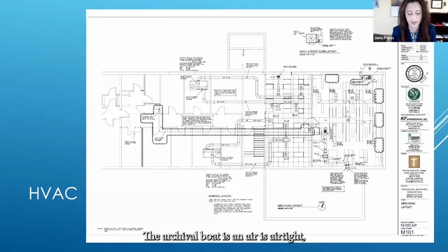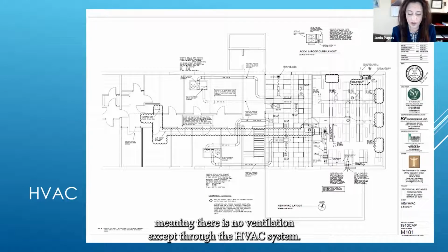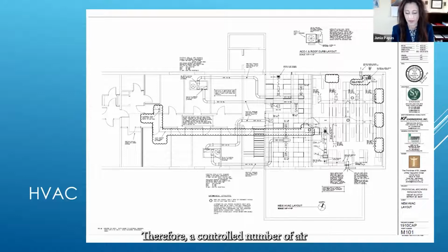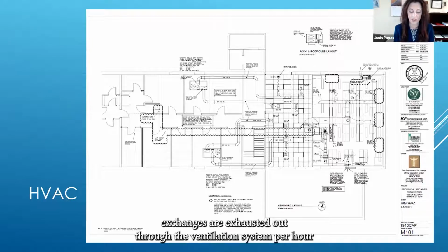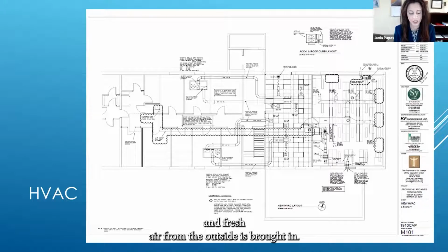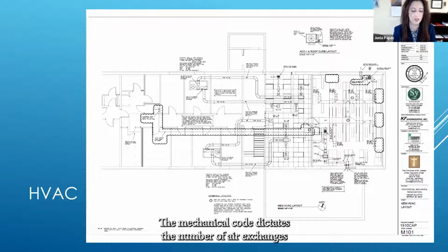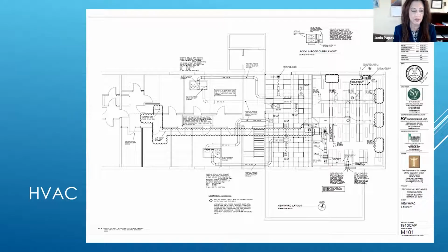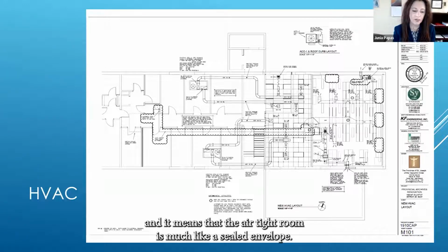The archival vault is airtight, meaning there is no ventilation except through the HVAC system. Therefore, a controlled number of air exchanges are exhausted out through the ventilation system per hour, and fresh air from the outside is brought in. The mechanical code dictates the number of air exchanges determined by the square footage of an occupied room. This is called the room's envelope, and it means that the airtight room is much like a sealed envelope.